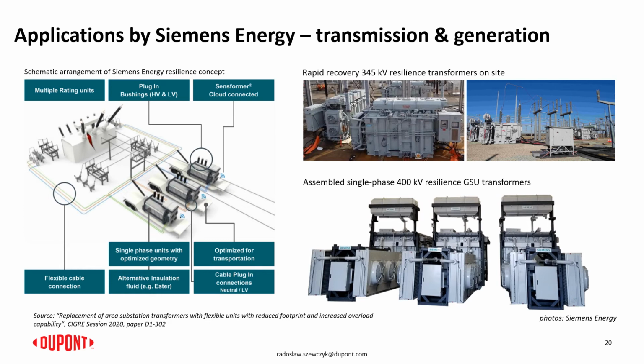produced by Siemens. On the left-hand side, we can see the project at Consolidated Edison in New York, where the trial installation of 3 units of 100 MVA was made, and this was with the record time of 30 hours of labor for installing and connecting those transformers to bypass the 300 MVA unit. In real case, the unit did not fail. It was just a trial installation, but the exercise showed that the installation or bypassing the 300 MVA transformer was available within those 30 hours of work.